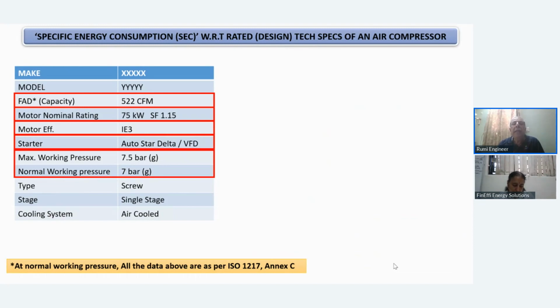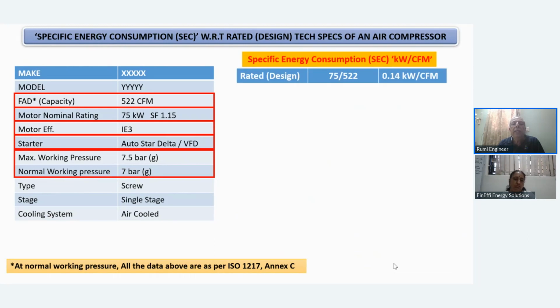So when I did a deep dive and asked facility people to share technical details, I said, boss, your design criteria when evaluating specific energy consumption, you say it's 0.14. Actually it is not 0.14. The manufacturer has clearly stated a motor is designed to take 75 multiplied by 1.15, that is 86.25. So ultimately it is 0.16 kW per CFM.